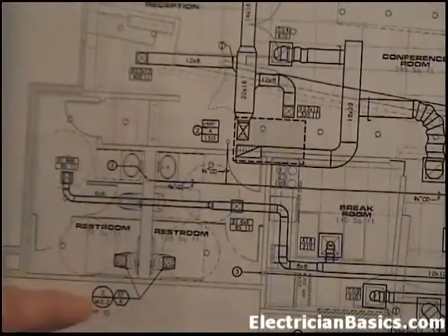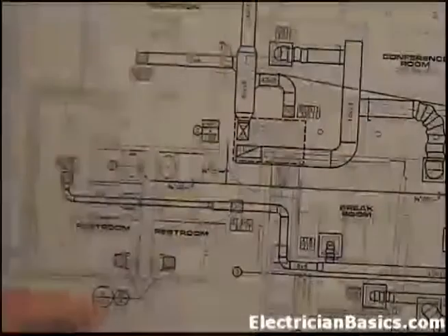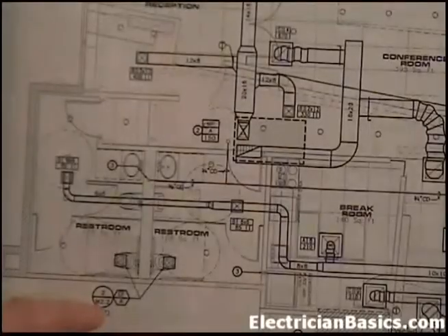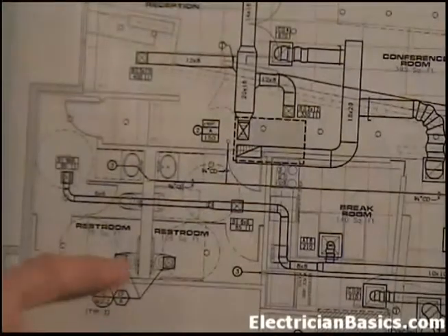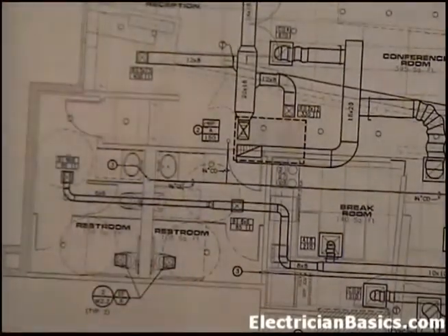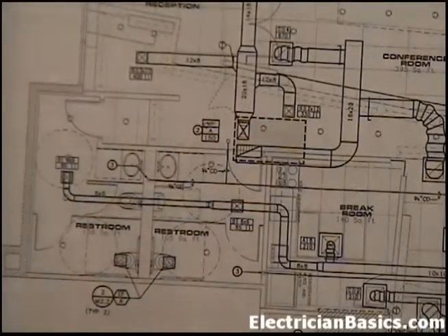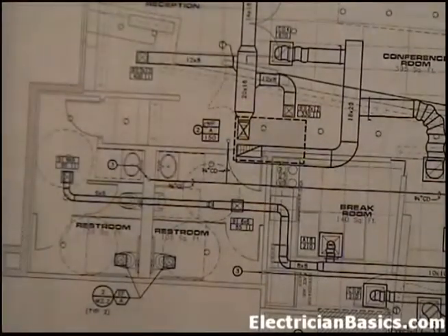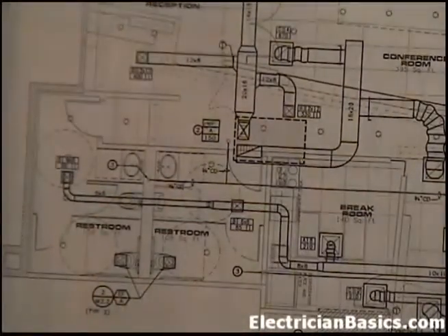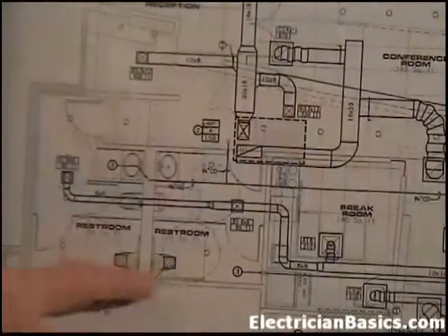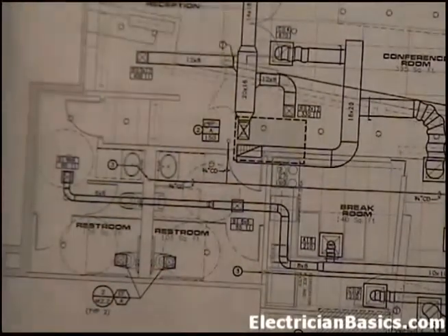Now this circle that's split in half points to M2.2, meaning you will find on page M2.2, detail 2, this exhaust fan. We talked about that page earlier, and we got a detail on one of the ducts that went in between the lights when we were on the reflected ceiling plan page. So when we get to that page, I'll point that out. Now it says right here TYP2, typical 2. In other words, there are 2 of those, typical for both of these 2.